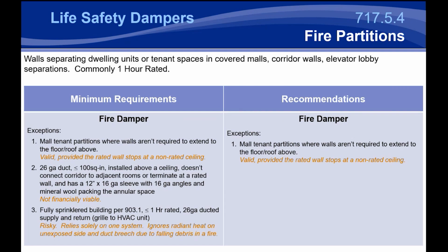They were used in covered malls, but those aren't really being built much nowadays. You may see them in elevator lobby separations as well. So some of the exceptions are valid, but are not commonly used. But there is a lesson to be learned with that exception. If you have a fire partition that doesn't extend from deck to deck, so the wall stops at, say, a non-rated ceiling, or doesn't go all the way to the floor above, then there really isn't a lot of protection that can be made with a damper in that wall penetration.